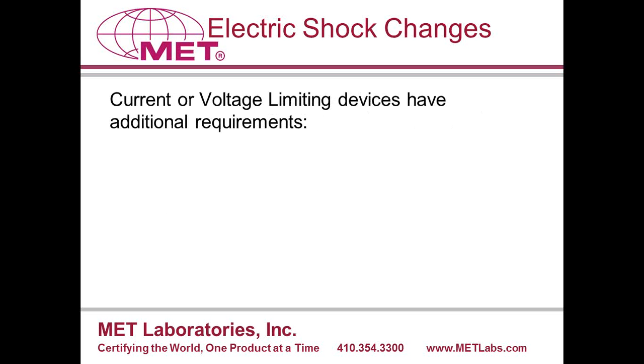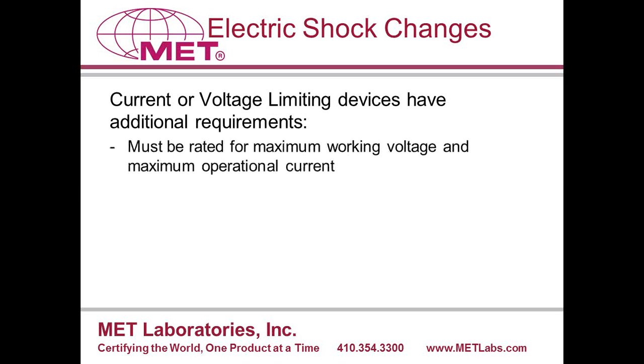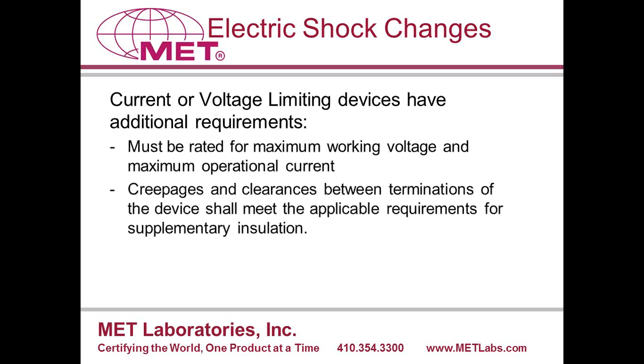There are also component selection and layout requirements when using current or voltage limiting devices. The ratings of each limiting device must be sufficient for the voltage and current. The spacings on the board for each component must meet creepage and clearance values for supplementary insulation.